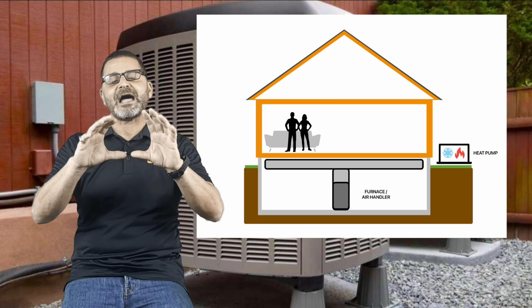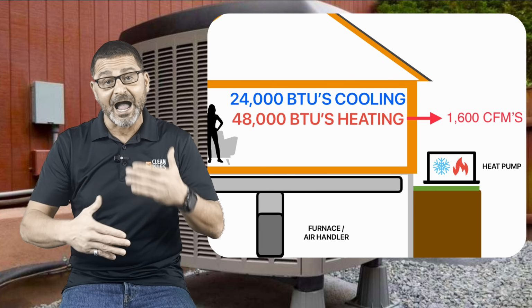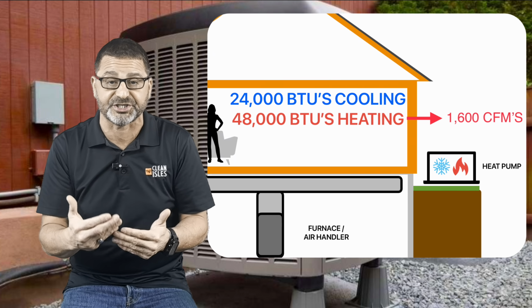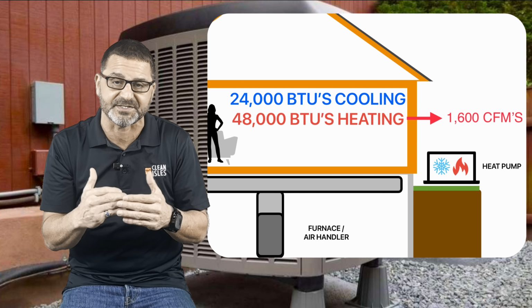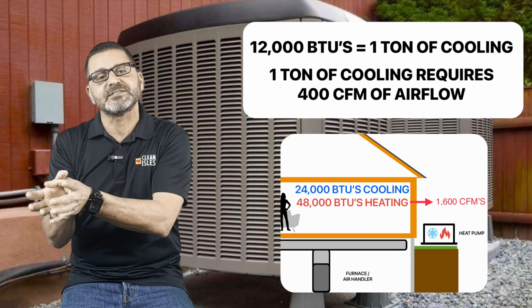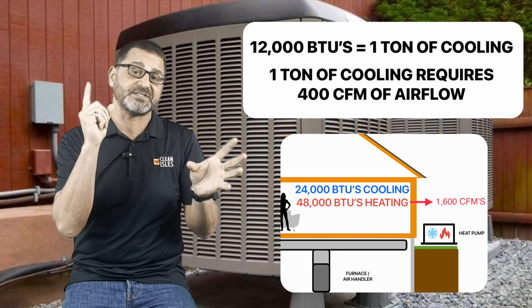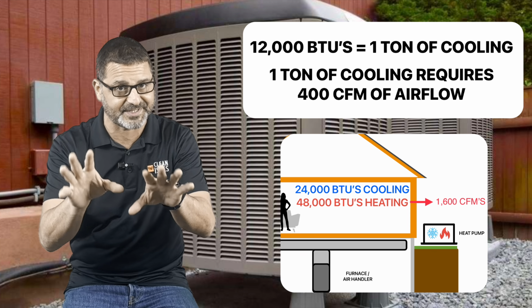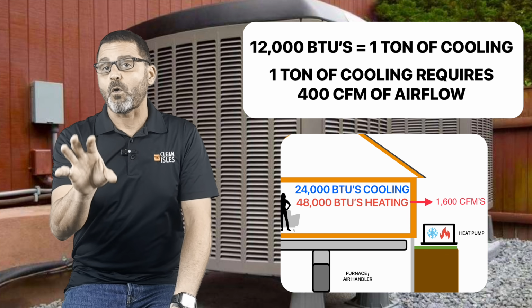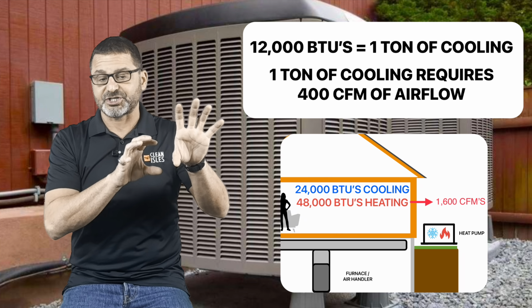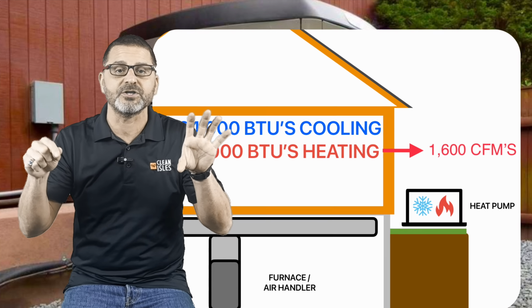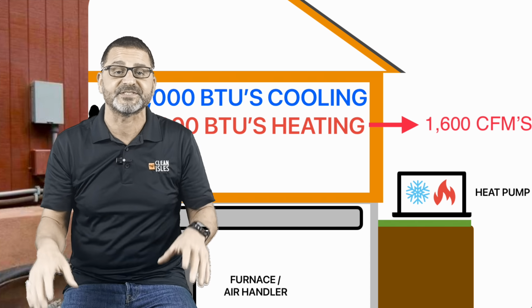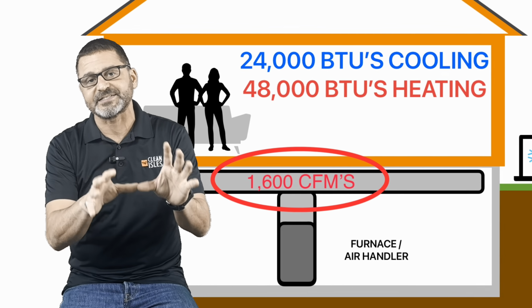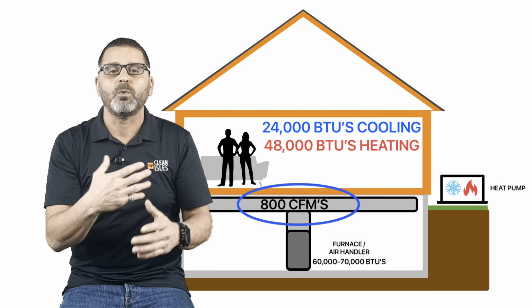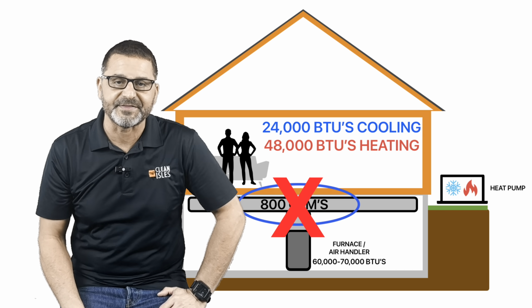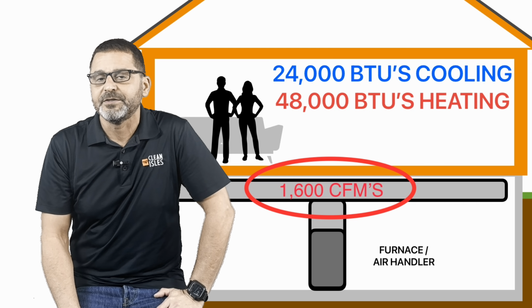Now, if I wanted to take that house and actually turn it into a heat pump system, I would have to double up that air conditioning to get to that 48,000 BTU system. So if I have a 48,000 BTU system and 12,000 BTUs is a ton and 1 ton is 400 CFM, stay with me, you would need a 4-ton air conditioner, which would be 4 times 400, or 1,600 CFM. That means that the original ductwork that's in there, that's normally 800 CFM, will not work. So we would have to upgrade that to a 1,600 CFM system.